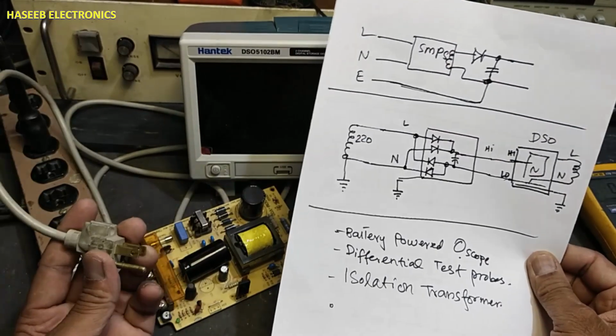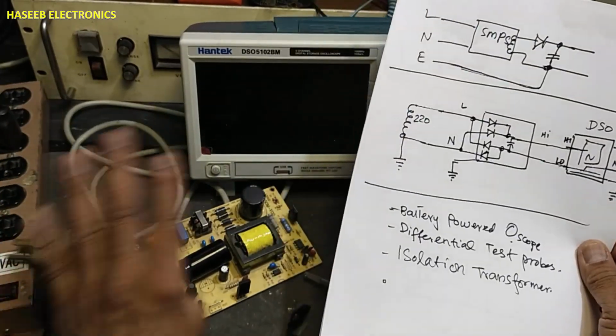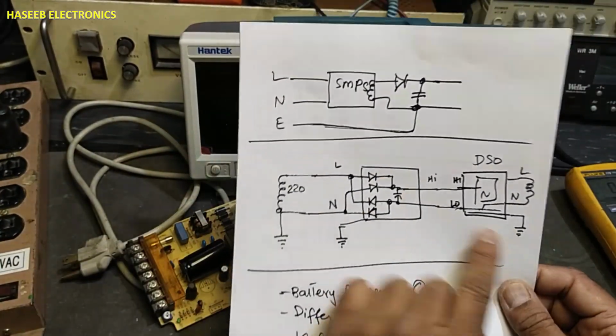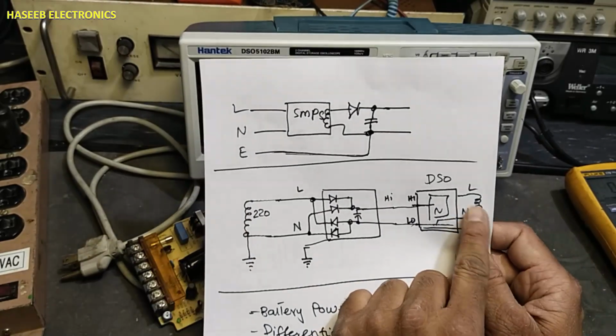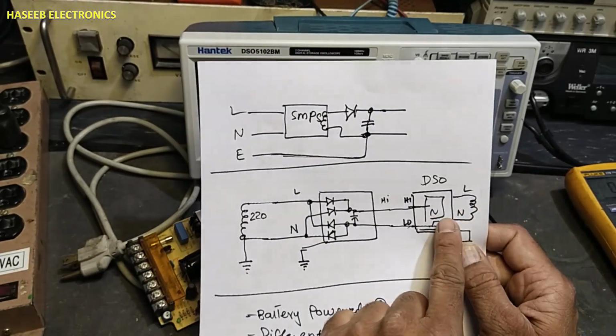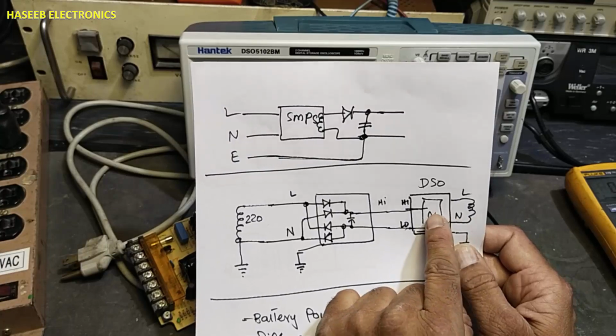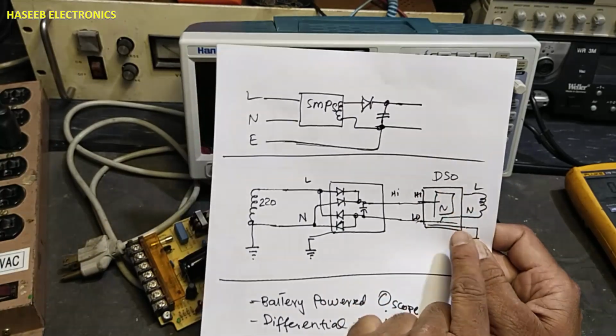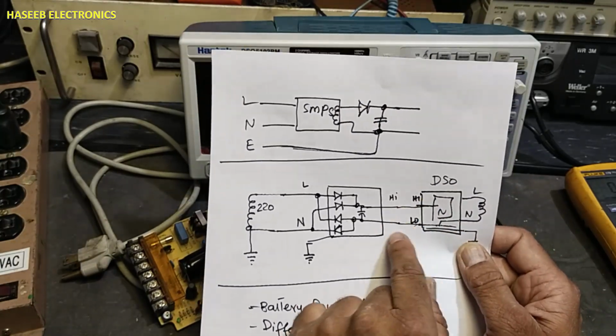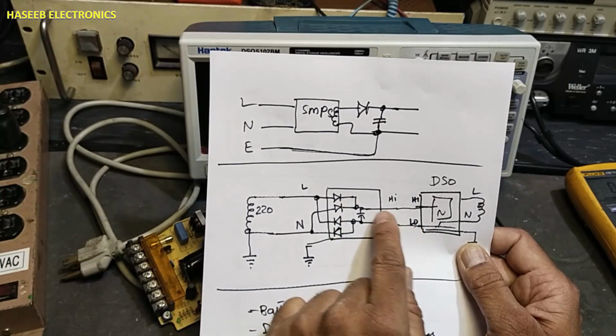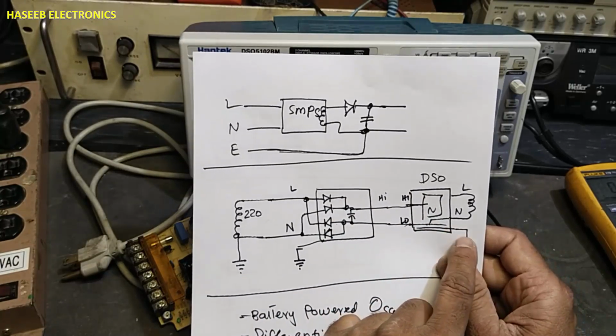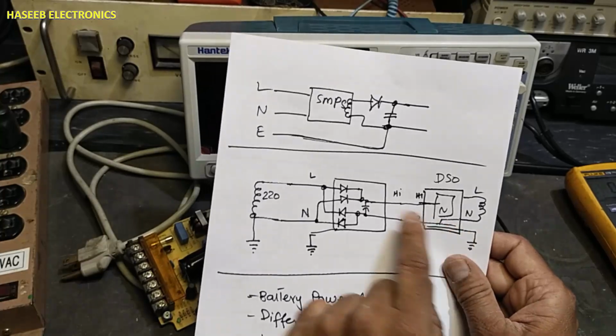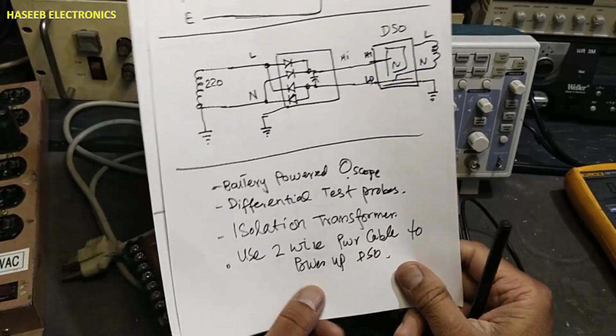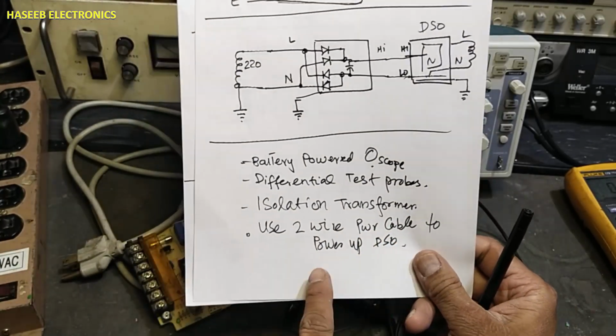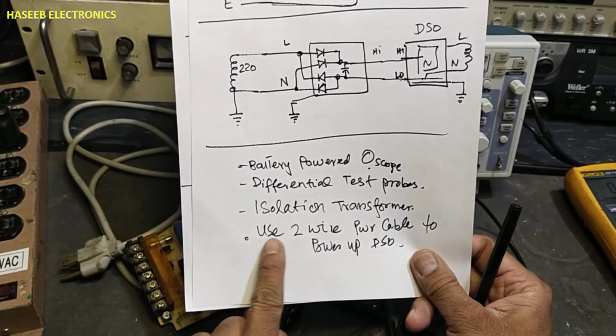If you use a 2-pin plug and power up the oscilloscope with direct line voltage, then line and neutral will reach the oscilloscope power supply, and if you test any circuit at that time, it will not be exposed to ground and we will not damage anything. Use a 2-wire power cable to power up the DSO - this is also a solution.